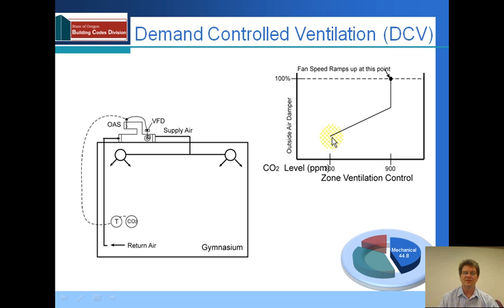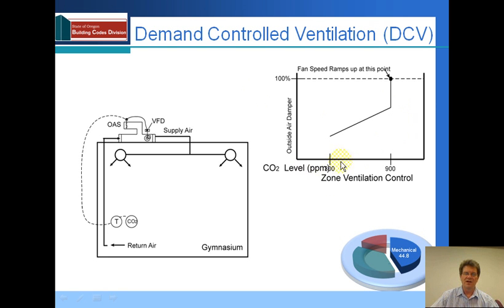So as the CO2 concentration rises because people are breathing in and out, it will open up the outside air damper to provide ventilation and meet ventilation requirements. However, when the space is empty and we have lower levels of CO2, the outside air damper will be closed and we will save energy. Thank you.